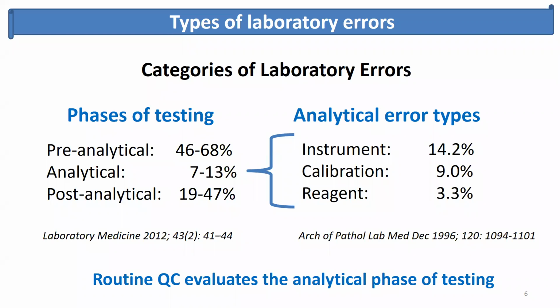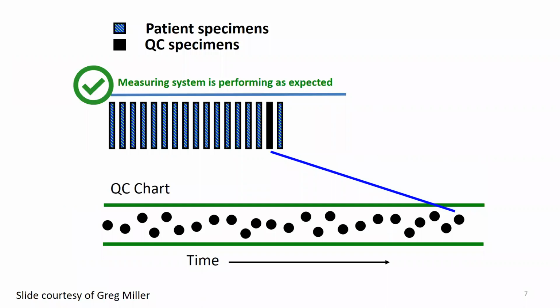The laboratory's routine quality control program should be designed to evaluate the analytical performance of the measuring systems and to detect potential errors in the analytical phase of testing. To monitor the analytical phase of testing, QC materials should be integrated into the patient testing workflow and analyzed along with patient specimens at a frequency established by the lab. For example, a laboratory may run QC every shift or every 12 hours.